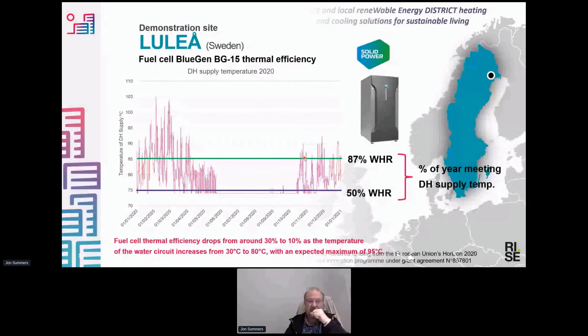Just quickly, I realize I do have a habit of speaking too much. So some lessons learned so far: we will operate the data center between 10 and 60% utilization, which is common for a lot of data centers. That means we have sufficient power from the fuel cells to operate, but we do not think we'll be able to match the district heating supply temperature all year round. That's the test we're going to run for 1 year to see whether we can.